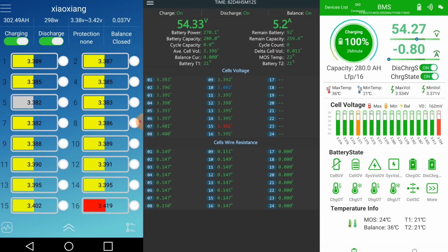All three battery banks were 100% calibrated at 3.62 volts for each of the cells in each bank, so it was 100% top balanced. Then on the left and on the right I left the active balancer running, while the one in the middle has its own active balancer, which only kicks in if one of the cells is over 3.45 volts, which was never the case in the last 2 weeks.